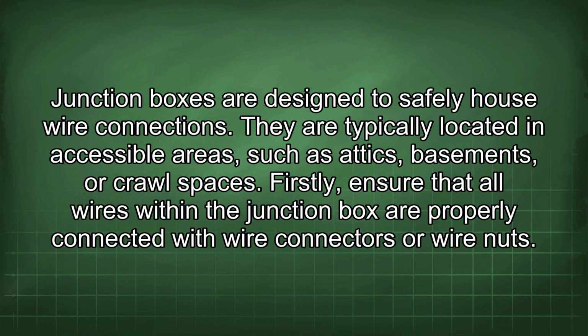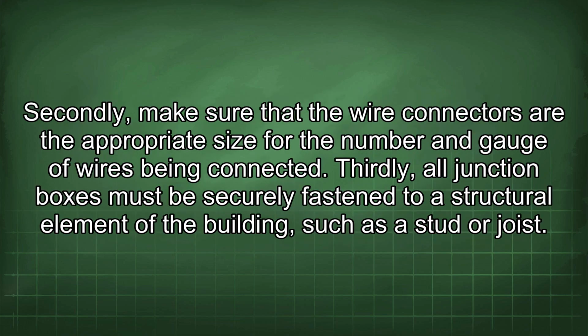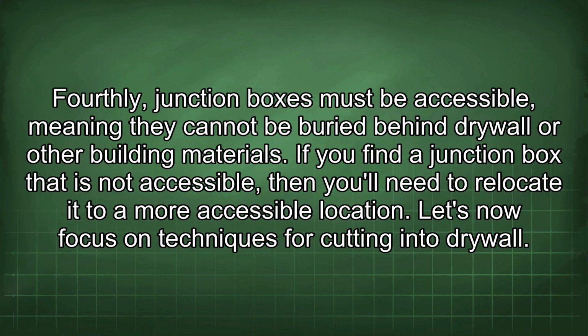Firstly, ensure that all wires within the junction box are properly connected with wire connectors or wire nuts. Secondly, make sure that the wire connectors are the appropriate size for the number and gauge of wires being connected. Thirdly, all junction boxes must be securely fastened to a structural element of the building, such as a stud or joist. Fourthly, junction boxes must be accessible, meaning they cannot be buried behind drywall or other building materials.